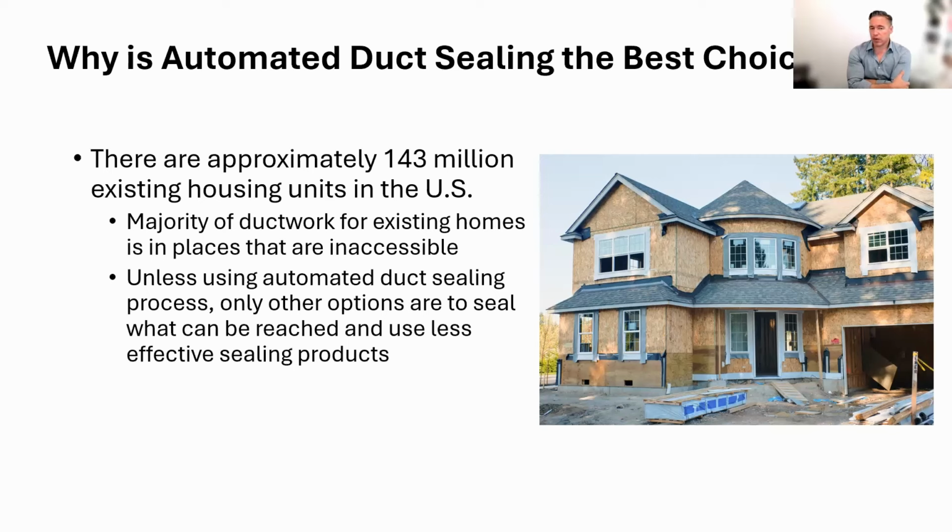We used to be out there sealing our new construction ductwork at rough-in, before the air handler was in place, which would work for code, but for Energy Star we have to test across that air handler. So we're waiting a little longer, getting out there a little later, sealing, and then removing all our plugs and testing across the entire system to make sure all of that leakage is included in our testing.